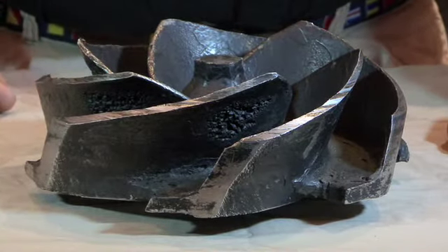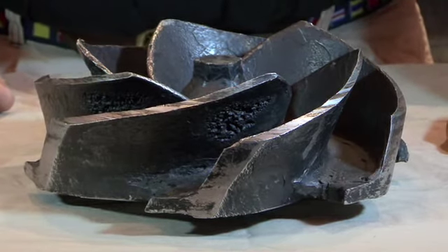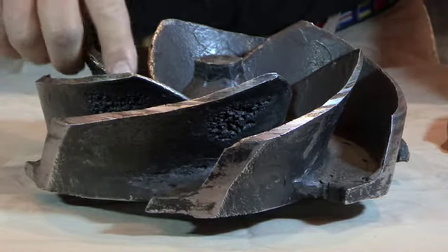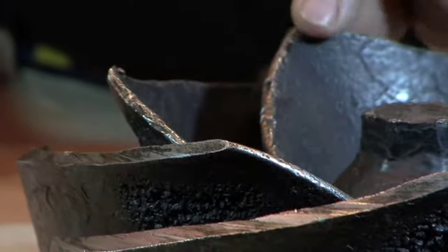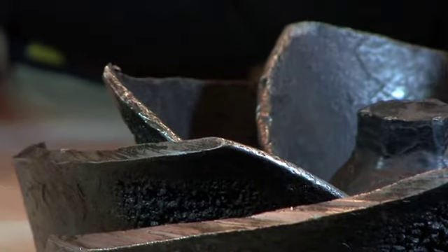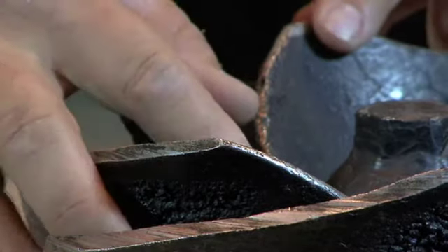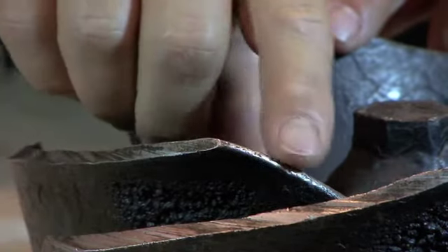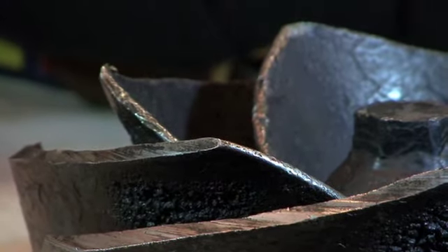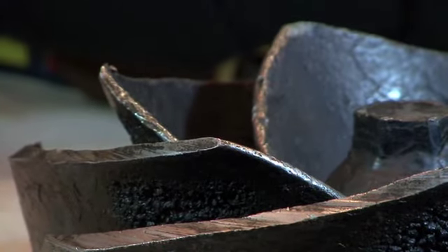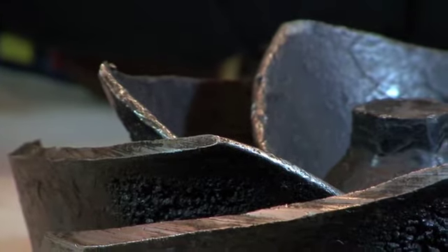Another feature to note here is as we look at the leading edge of these impeller blades, right here and particularly right here. If we look at this right here, you see all those indentation marks right there? You can actually see it right on this one. You can see it here as well. You can see it on this one. These marks and damage that are actually indenting indicate that this impeller was seeing a bunch of debris come through it. So it had its problems.